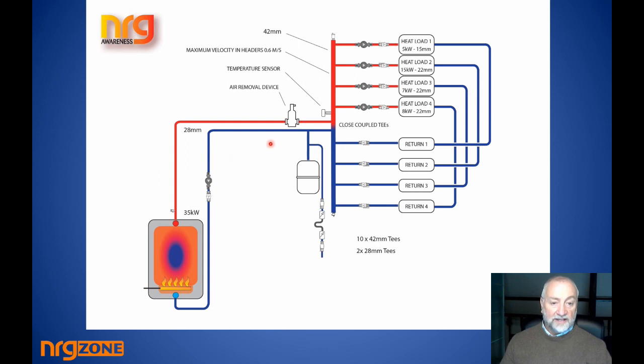And likewise, when it gets to the header situation, manufacturers would recommend that if you have a 32 kilowatt, or sorry, a 35 kilowatt boiler, just suppose, that you would go all the way up to a 1.5 inch header to carry that heat at the very least, right? There's a reason for that. You don't want a given zone or a group of zones to be drawing so much flow that they cause it to pass another zone that needs fluid. So you want as little resistance as is possible within the flow and return headers.